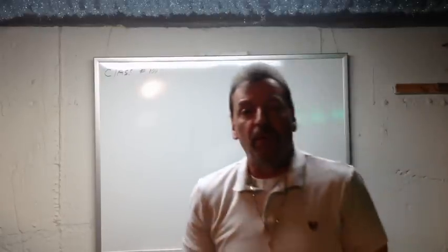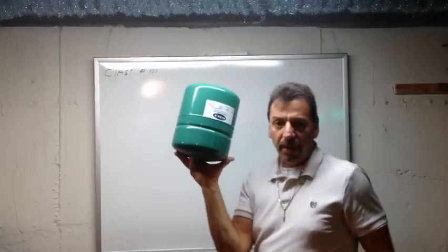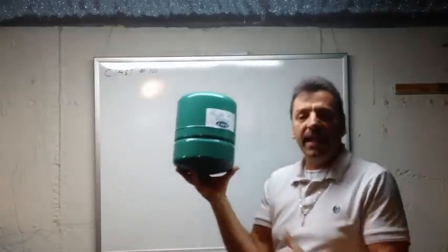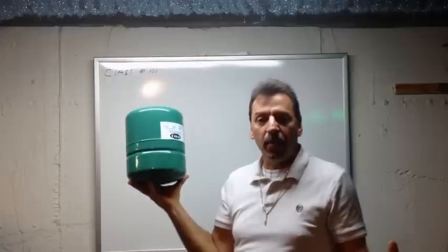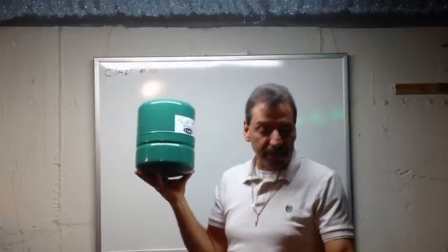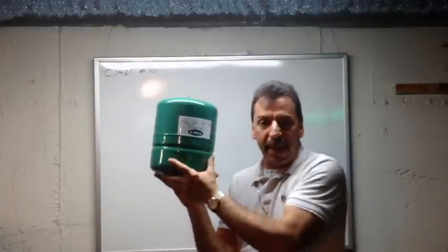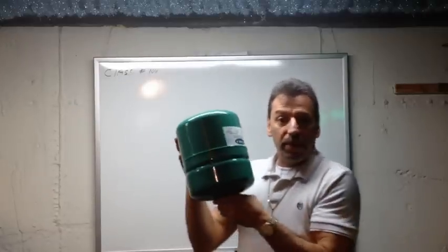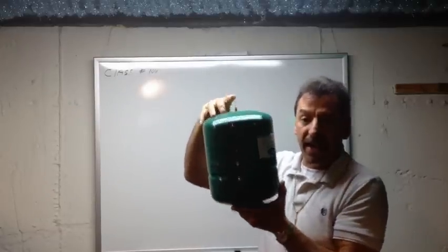The other reason the boilers can release water out of the relief valve is the expansion tank that's on the boiler. Now, this is on every boiler also because as the water heats up, it expands and needs somewhere to go. Instead of dripping out the relief valve, it takes the expansion. This is by design. This also comes with air, pressurized air, inside this little bicycle valve with 12 to 15 PSI in it.